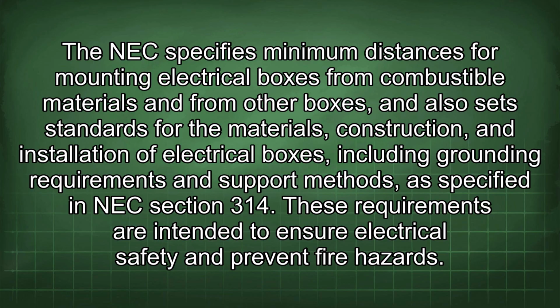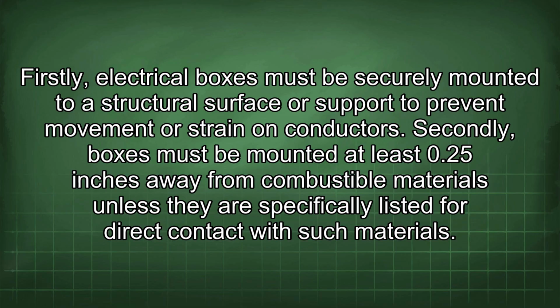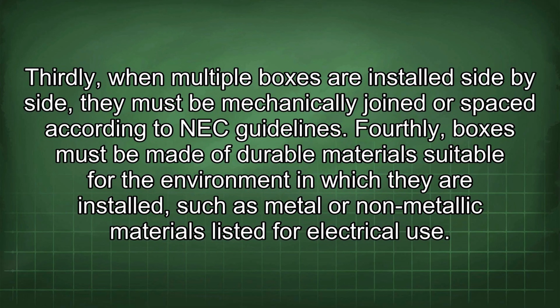The NEC specifies minimum distances for mounting electrical boxes from combustible materials and from other boxes, and also sets standards for the materials, construction, and installation of electrical boxes, including grounding requirements and support methods as specified in NEC Section 314. These requirements are intended to ensure electrical safety and prevent fire hazards. Firstly, electrical boxes must be securely mounted to a structural surface or support to prevent movement or strain on conductors. Secondly, boxes must be mounted at least 0.25 inches away from combustible materials unless they are specifically listed for direct contact with such materials. Thirdly, when multiple boxes are installed side by side, they must be mechanically joined or spaced according to NEC guidelines. Fourthly, boxes must be made of durable materials suitable for the environment in which they are installed, such as metal or non-metallic materials listed for electrical use.